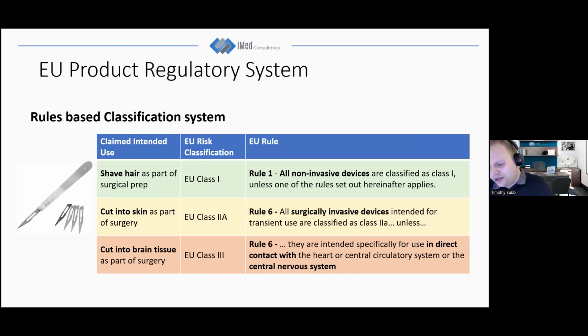So the US and the European system have two slightly different ways of identifying what the level of risk is. So the European system uses what's called a rules-based classification system. So using that same example that we were taking a look at before for medical devices, shaving hair comes under what's called Rule 1. And this is essentially a rule for all devices that don't fit into other categories. It also comes under two parts of Rule 6 within the European system. So Rule 6 looks at surgically invasive devices, unless another category within that rule applies, which is where Class 3 comes in for cutting into brain tissue. So because you're cutting into brain tissue, you are in direct contact with the central nervous system.